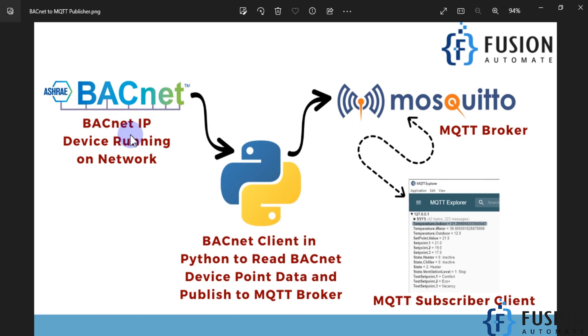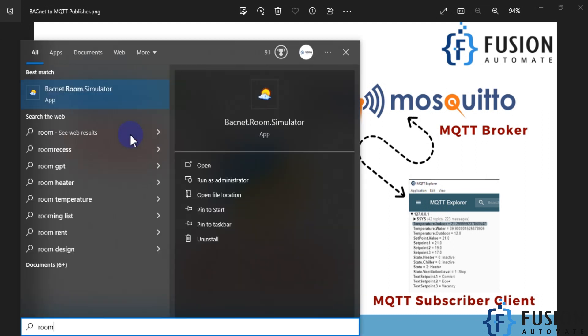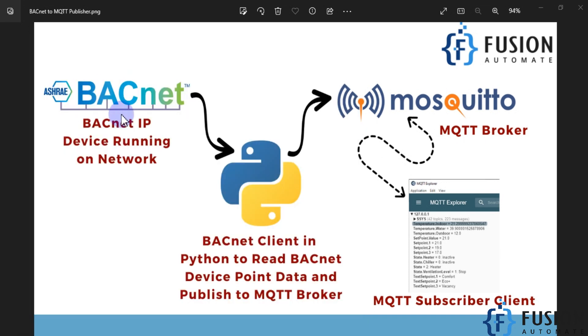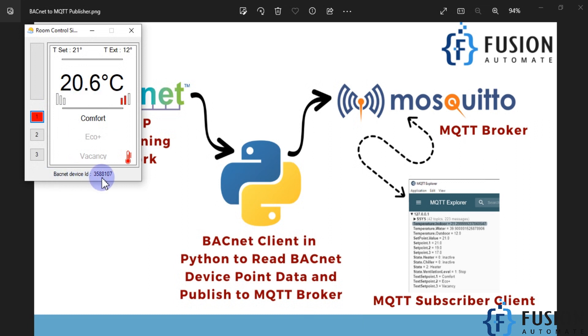This BACnet device will be our room simulator. If you have installed YABE software — I will provide the link in the description — you will get this BACnet room simulator. Once you run it, you can see it is acting as a BACnet device from your system. You can check here that the BACnet device ID is available, so our BACnet device is up and running.